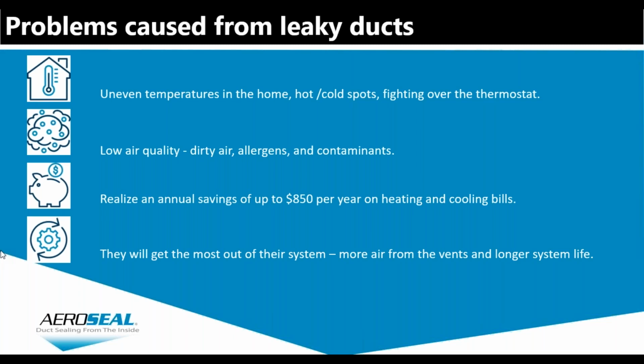So again, adding on to that, the equipment will often need to run longer because of the comfort issues in the home. When they're cranking the thermostat setting up or down, trying to get the temperature in the space perfect, they're actually compounding the waste of energy. And that goes into the next point: they're going to get the most out of their system. Even on new system installs, with leaky ducts, they're not performing to the efficiency level that they're rated at, and it may cause premature system failure.